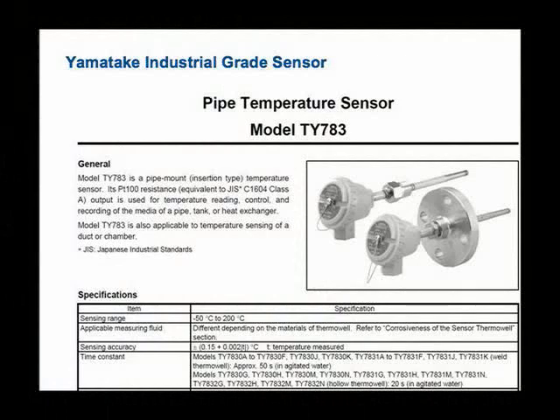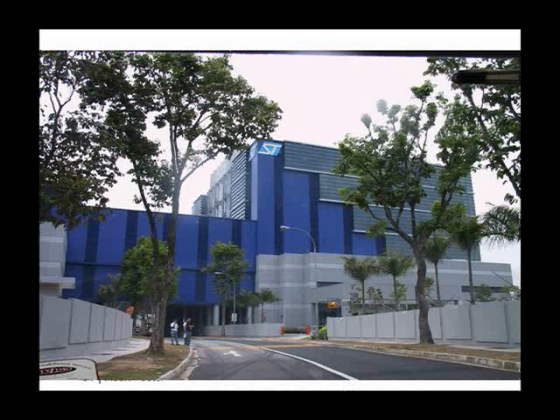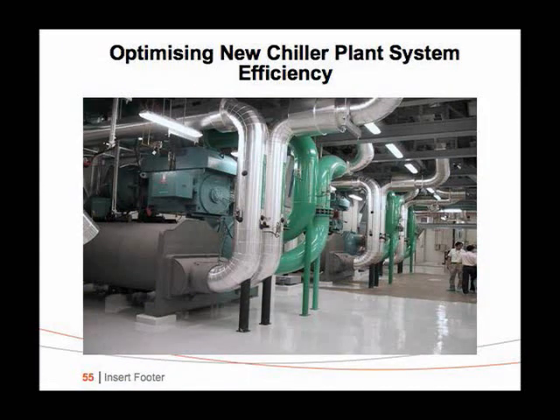Yamatake is a very well-known vendor, at least in Singapore, for industrial systems, and their sensor is 0.15 degrees C. So at the start, this is five times worse than what we need for ARI 550. So here's an example of the Negawatt thinking. A new fab was set up. We've done work for this client, new machines, a bunch of 2,000 tons.